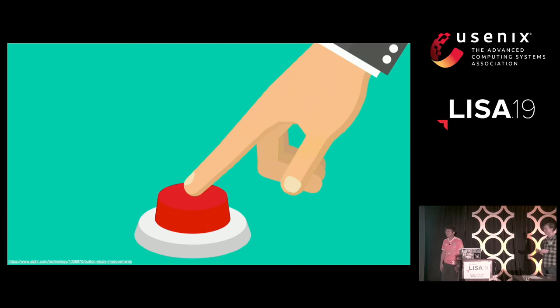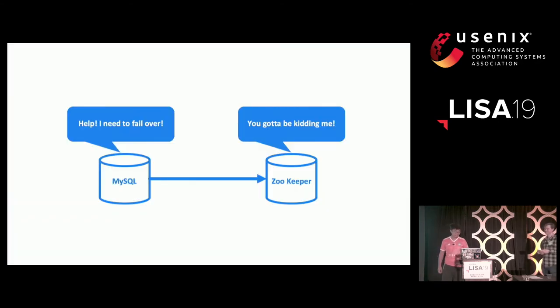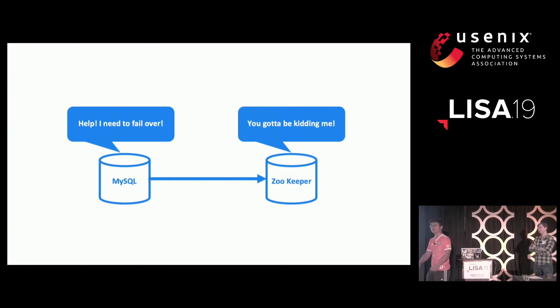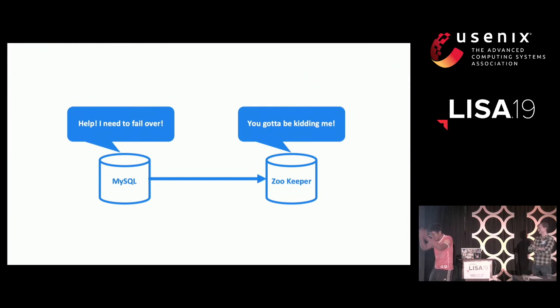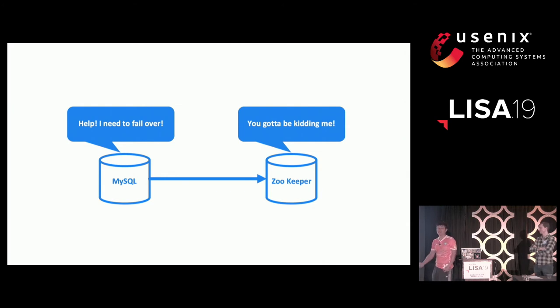But what happened? How could we be wrong — we had the auditor. It turns out that this switchboard powered thousands and thousands of MySQL servers, and they all needed to failover when power went off. The way they failover is by writing to a coordination service called Zookeeper, basically saying 'I'm dying, please elect a new master.' But because thousands and thousands of MySQL servers failed at exactly the same time, Zookeeper could not keep up with the sudden instantaneous load. So the failover failed for many MySQL servers, and everything that depended on MySQL to write or read data failed.